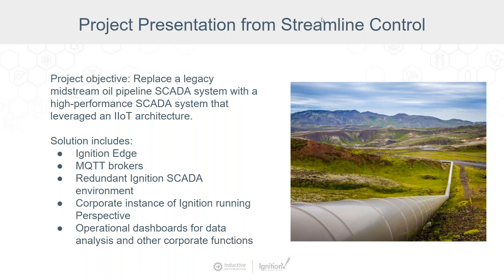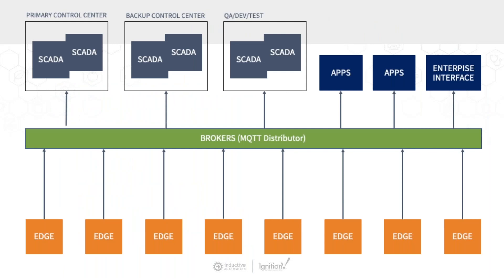The best way to look at this is to see what Streamline built from an architecture perspective. We use MQTT Distributor as our middleware operational backbone — brokers distributed at each control center, sitting at layer 3 and below for Purdue model compliance. Edge nodes are distributed throughout the pipeline system. Communication is through VSAT and cellular, allowing for two communication paths. The edge can swap between communication mediums seamlessly using Cirrus Link's MQTT modules, which have path-swapping built into the product.